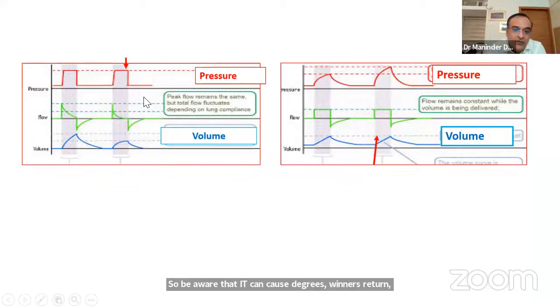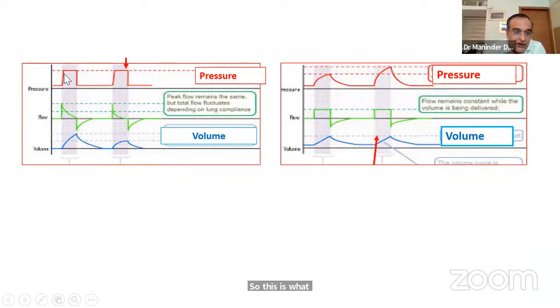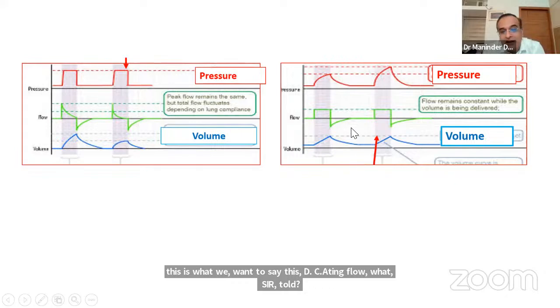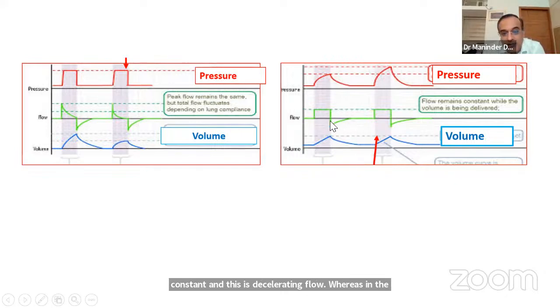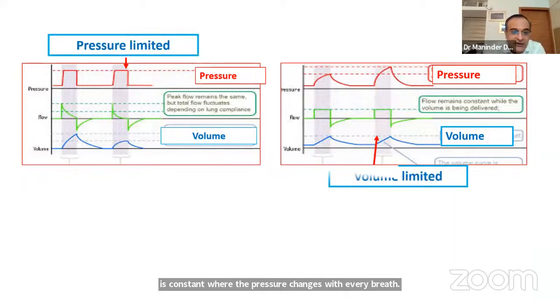So this is what we want to say about this decelerating flow, what Sir told. This is the pressure mode. Over here, the pressure remains constant and this is decelerating flow. Whereas in the volume mode, the volume remains constant and the flow is constant, whereas the pressure changes with every breath.